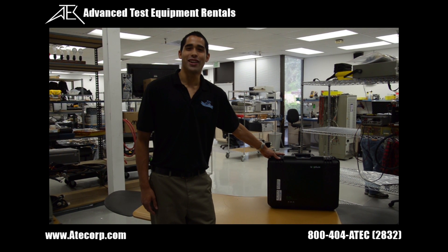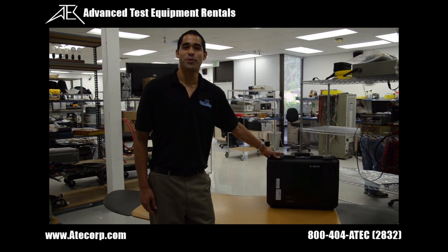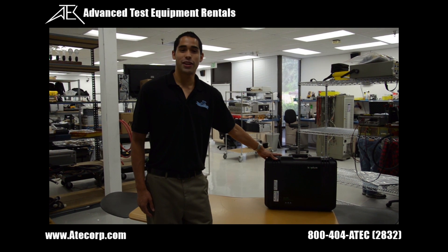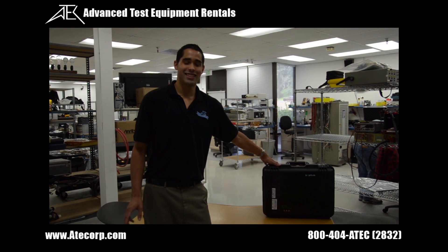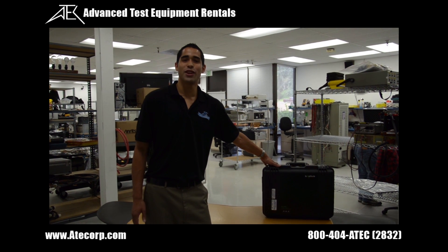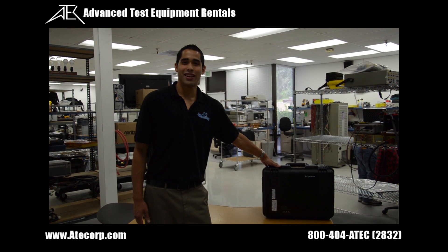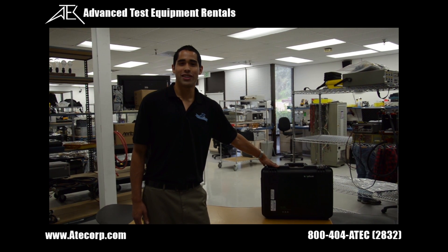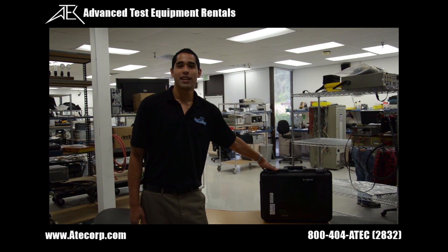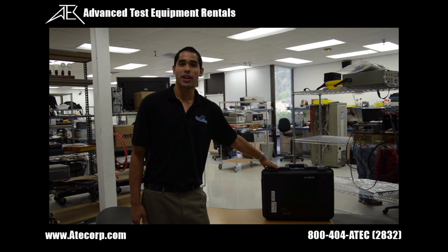Hi there, my name is Gabriel from Advanced Test Equipment Rentals and we're here today to go over Kaelus' new iPA series PIM tester. We're going to go over the testing of the low PIM load and also the PIM source, which are required tests before you actually get testing to ensure the PIM tester is actually working correctly.